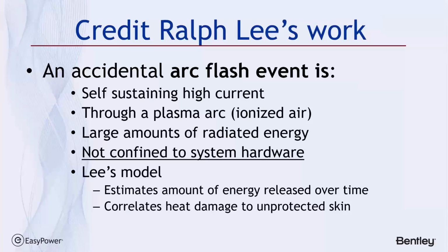He called it an arc flash event, and defined it as a self-sustaining high current event where the current is going through a plasma arc, which is ionized air. The event releases large amounts of radiated energy, and it's not confined to the system hardware. I underline this because that was the major problem as far as defining the hazard, is that the system could be designed to deal with a fault, but not necessarily a fault that was outside the path of the system itself. So Lee's model estimates the amount of energy released over time and correlates the heat damage to unprotected skin.